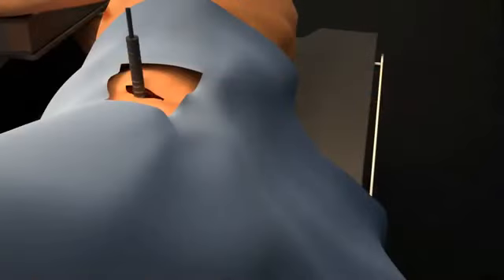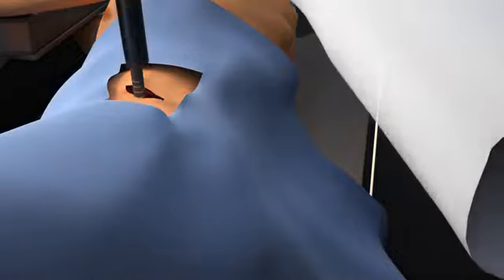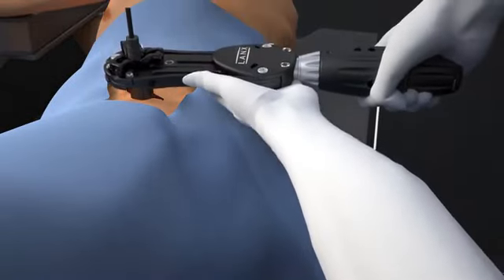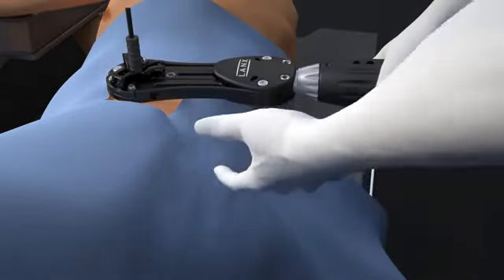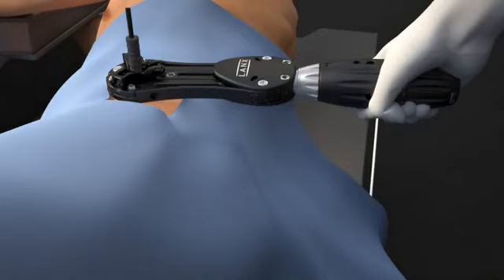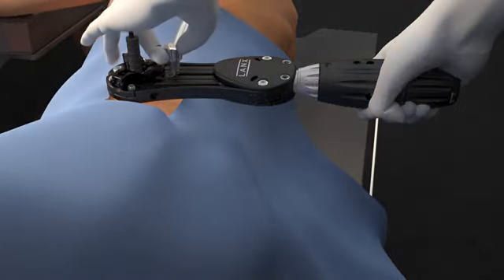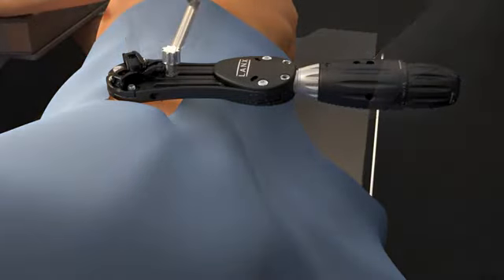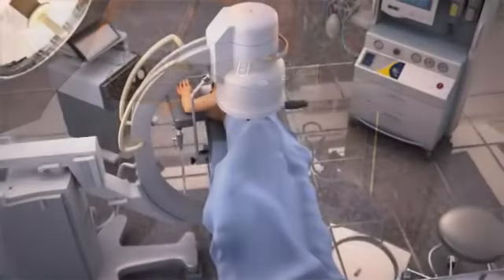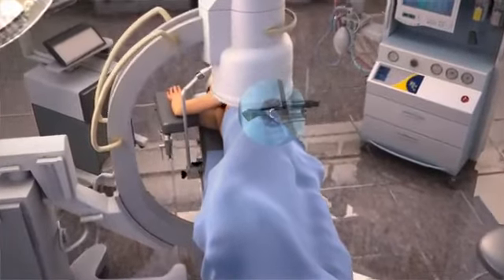Employ a rotating motion with downward pressure until the blades are seated on the disc space. Confirm using AP fluoroscopy. Orient the retractor such that it is in line with the disc space and parallel to the floor. While maintaining downward pressure on the retractor, attach the articulating arm. Attachment to the center arm will allow for anterior retraction, while attachment to the retractor body will allow for posterior retraction.